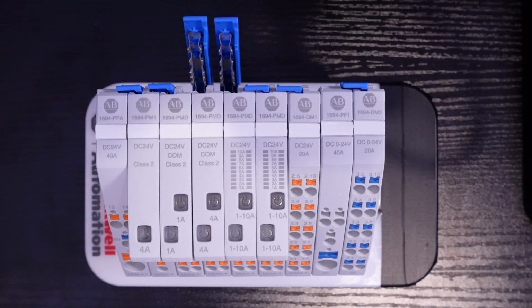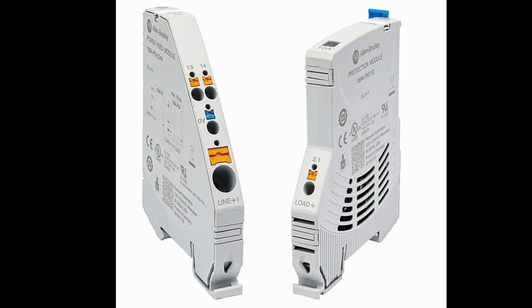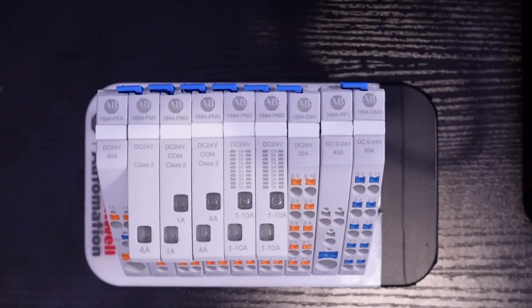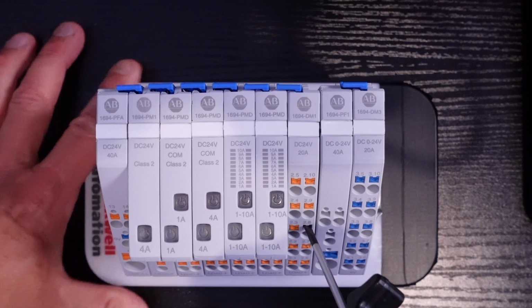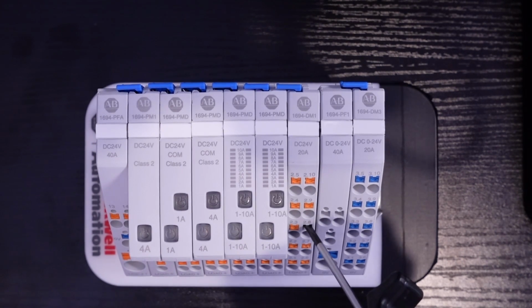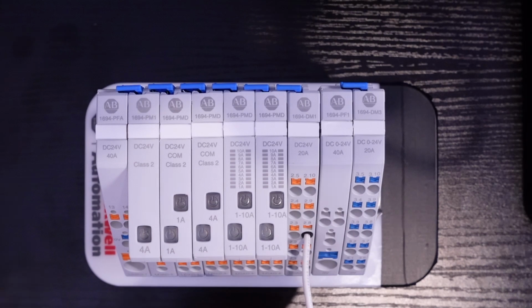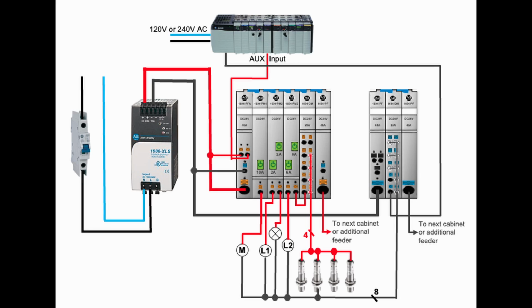As you can see, it's a modular, easy to install system that's comprised of two main components: a power feed module and the protection modules. The components are mechanically and electrically connected by swing arms, so there's no inner wiring. Connection to the field devices is simplified with push-in style terminal connectors, and there are no accessories required. The power feed module accepts the incoming supply from a 24 volt power supply, and the protection modules provide the individual circuit protection and disconnecting means for each of the downstream devices.